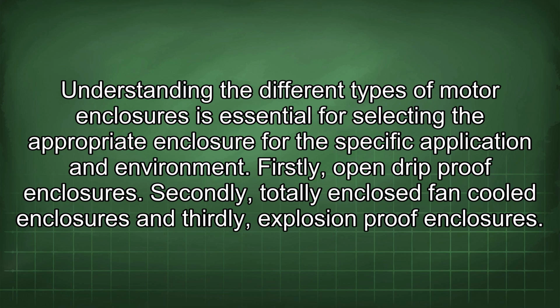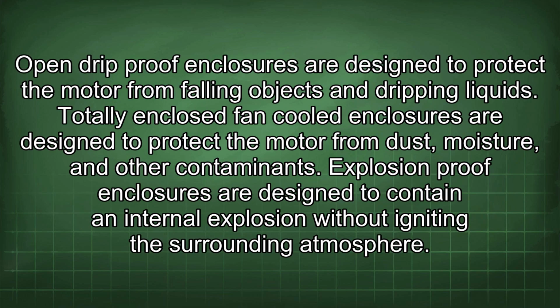Understanding the different types of motor enclosures is essential for selecting the appropriate enclosure for the specific application and environment. Firstly, open drip-proof enclosures. Secondly, totally enclosed fan-cooled enclosures, and thirdly, explosion-proof enclosures. Open drip-proof enclosures are designed to protect the motor from falling objects and dripping liquids. Totally enclosed fan-cooled enclosures are designed to protect the motor from dust, moisture, and other contaminants. Explosion-proof enclosures are designed to contain an internal explosion without igniting the surrounding atmosphere.